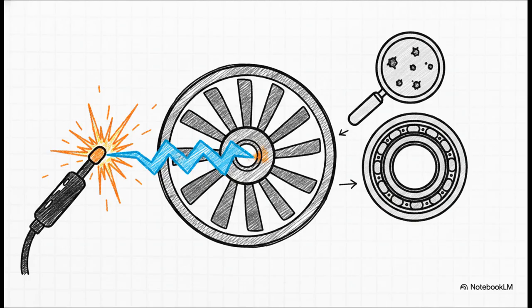There's also a very sneaky trap you have to watch out for when the engine is just sitting there off, and that's nearby welding. If someone is doing unauthorized welding near the package and they don't ground it properly, stray electrical current can jump right through the unpowered turbine rotor. That stray current arcs across the tiny, microscopic clearances inside the bearings. It causes this invisible pitting and brittling. You won't even know what happened, but that bearing is basically guaranteed to fail right after your next restart.